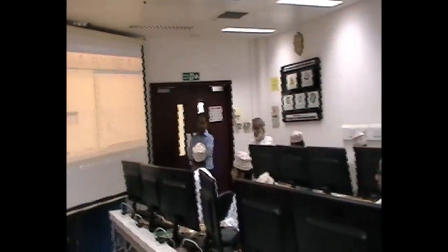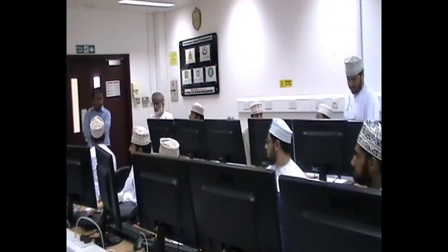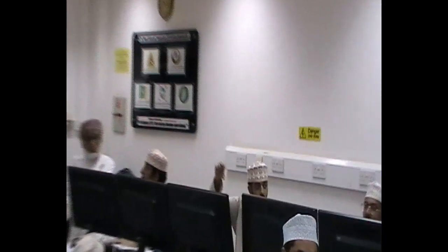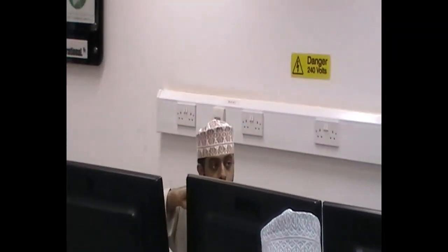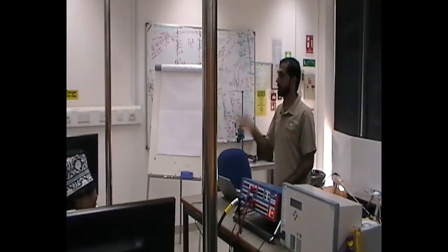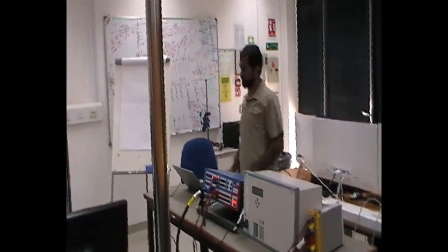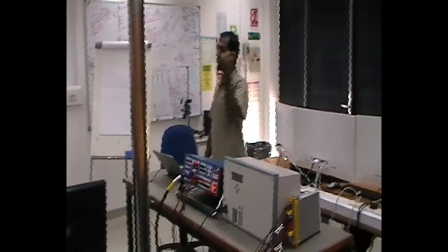Up to this point, it's 100% of the line. So zone 2 covers a little bit of the line and extends to whatever is beyond the line. It could be another line; usually we have transformers. But if we have another line, there should be another relay there. Yes, but again, zone 2 could be set to protect only the first 20% of that line. But about the second relay, will it consider it in zone 1? Forward only. Yes, it will consider it in zone 1, but it will not see in the back.